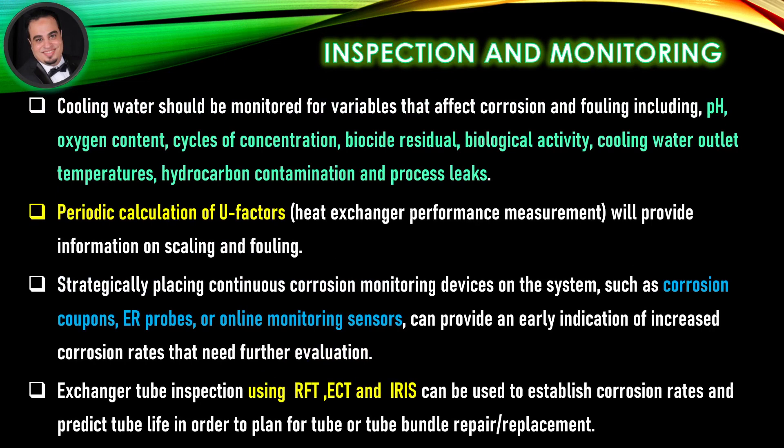Inspection and monitoring: Cooling water should be monitored for variables that affect corrosion and fouling, including pH, oxygen content, cycles of concentration, biocide residual, biological activity, cooling water outlet temperatures, hydrocarbon contamination, and process leaks. Periodic calculation of U-factors as a heat exchanger performance measurement will provide information on scaling and fouling.